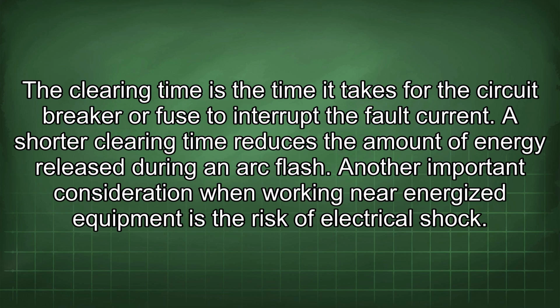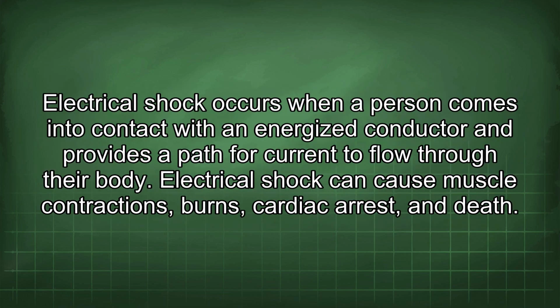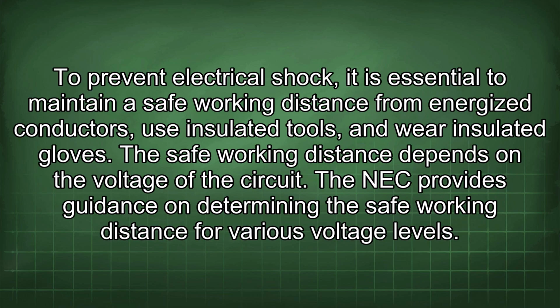Another important consideration when working near energized equipment is the risk of electrical shock. Electrical shock occurs when a person comes into contact with an energized conductor and provides a path for current to flow through their body. The electrical shock can cause muscle contractions, burns, cardiac arrest, and death. To prevent electrical shock, it is essential to maintain a safe working distance from energized conductors, use insulated tools, and wear insulated gloves. The safe working distance depends on the voltage of the circuit. The NEC provides guidance on determining the safe working distance for various voltage levels.